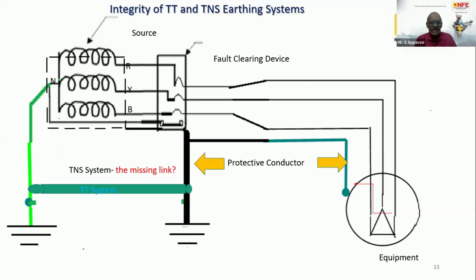So 99.9%, this will be in the order of milliohm, whereas the earth electrode will be in the order of ohms. Finally, it has to travel. Instead of 10 ohms, even with a very good value of 10 ohm, your milliohm path will take 99.9%. That's why the earth loop impedance concept with the TNS earthing system is insisted on in installation. But what we people are doing is the TT earthing system. So I don't discourage you from going for TT, IT, or TNS. These are just having a reference. Earth electrode only acts as a reference.